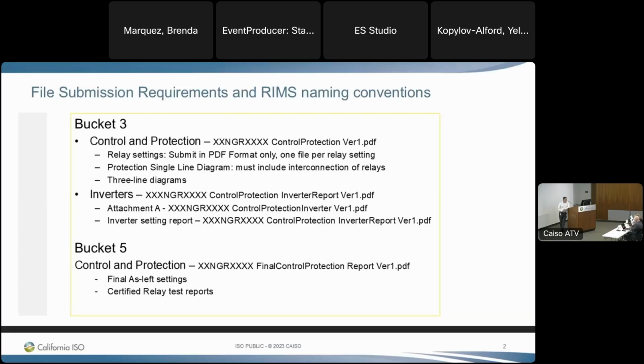Some important parts about the control and protection, which is basically the protective relays: we want them submitted in PDF. We don't want to have to pull application-specific software from SEL or someone to open up the settings. We'd like one relay per file. I know that makes a lot of submissions, but otherwise we end up with a 2,000 or 3,000 page document that's very difficult to search through and a little frustrating.